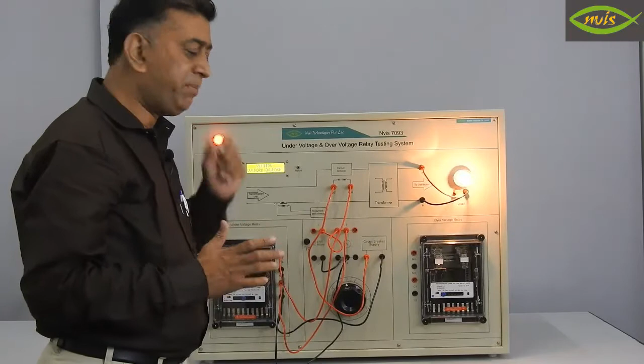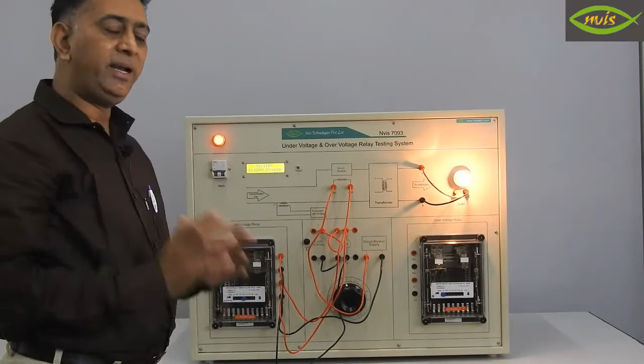Now you can see here, since the relay is tripped but the circuitry is on, you have to switch on this relay plunger. Now you can see this metallic plate has gone above and is stuck there because it is working as a solenoid this time. Due to this magnetization, it comes and sticks on the upper part of this solenoid. Now when I start to move this variac from 110 volt towards 0 volt, a point will come which is equivalent to your plunger setting, which is 65 volt. As you will see, when it reaches 65 volt, the relay will trip off, and it is the distribution safety which will be provided by the relay. This is the whole experiment we are going to perform.